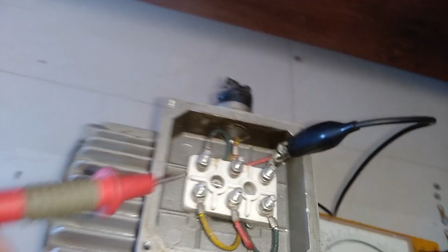It is not compulsory that you connect only the black probe. Any probe can go over there. So one probe is connected to the body, and the second probe will be connected to the phase. One by one we are going to check all three phases. So let's begin. First thing we do is check if the Megger is working fine. This Megger has an error of 0.5 mega ohms. Then we check the phase.